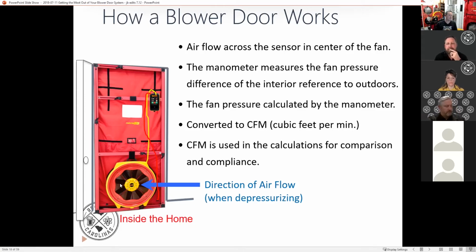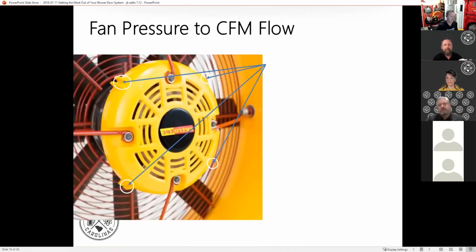And the last piece of how this calculates flow is that it's measuring the pressure in the fan, and then you have a known hole opening here on the inlet side. Since the manometer knows what the pressure is and it knows the area of this hole, those are the two things that you need to calculate flow. Back in the day, you had to do all that by hand. Now these manometers are like little handheld computers. It does all the math for you and makes it super fast and easy. For the fan pressure, there are these little ports around the center part of the fan that pick that up. I won't go too much into this. If it's a topic of interest, just let us know. We can dive deeper into the weeds later on.